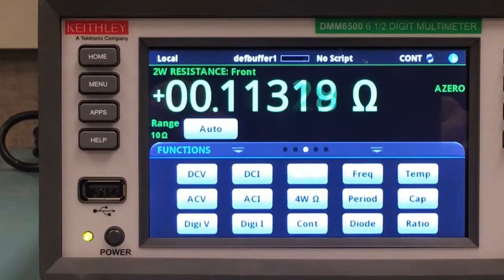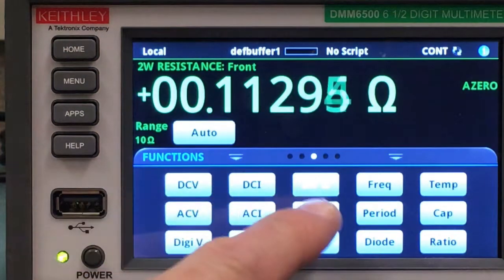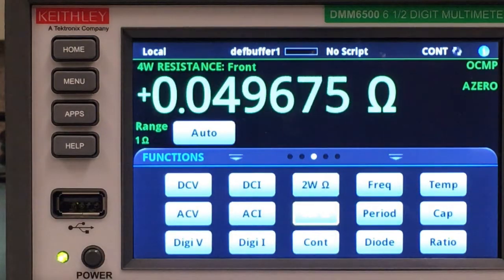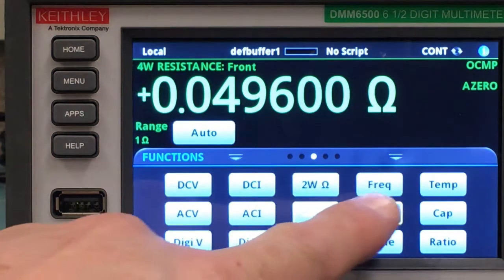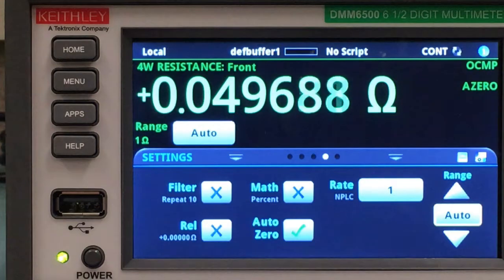I can then change my measurement function to four-wire, and you can see that we are very near the target value of 50 milliohms. Let's see if we can make that a little more eye-pleasing by applying a filter.